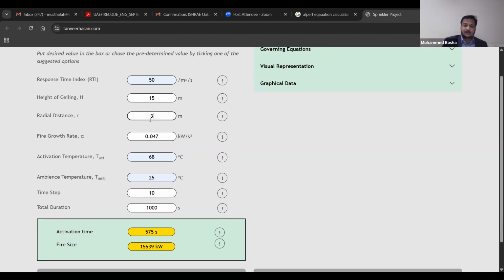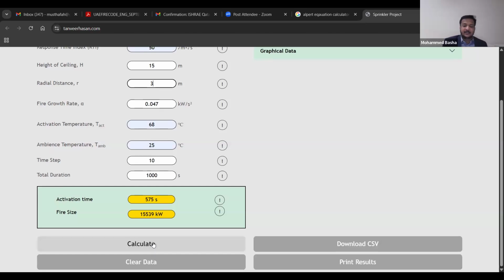So let us put the sprinkler at 3 meter distance from the fire. You need 7,558 kilowatt, half of that value. Now if you further reduce the spacing between the sprinklers, normally sprinklers need to be spaced at least a distance of 1.8 meter between the sprinklers. So you can put 2 meters also. So you are still reducing to 6,680 kilowatt. So at 377 seconds, the sprinkler will activate. 6,680 kilowatt is the fire size.